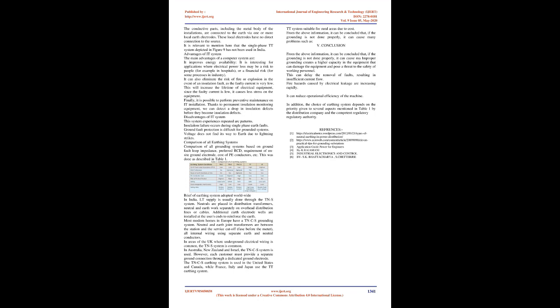Brief of earthing system adopted worldwide. In India, LT supply is usually done through the TNS system. Neutrals are earthed at distribution transformers. Neutral and earth work separately on overhead distribution lines or cables. Additional earth electrode wells are installed at the user's ends to reinforce the earth. Most modern homes in Europe have a TNCS grounding system. Neutral and earth are joined at the transformer, between the station and the service cutoff fuse before the meter, with all internal wiring using separate earth and neutral conductors.